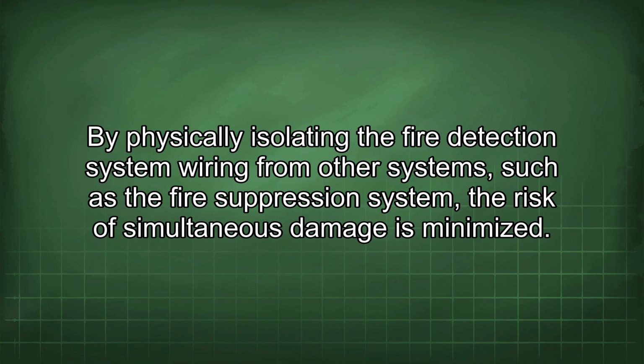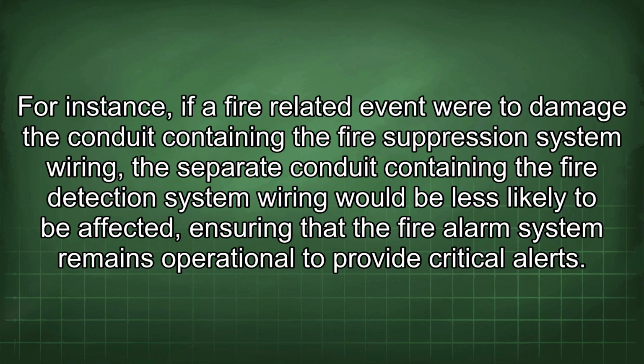By physically isolating the fire detection system wiring from other systems, such as the fire suppression system, the risk of simultaneous damage is minimized. For instance, if a fire-related event were to damage the conduit containing the fire suppression system wiring, the separate conduit containing the fire detection system wiring would be less likely to be affected, ensuring that the fire alarm system remains operational to provide critical alerts.